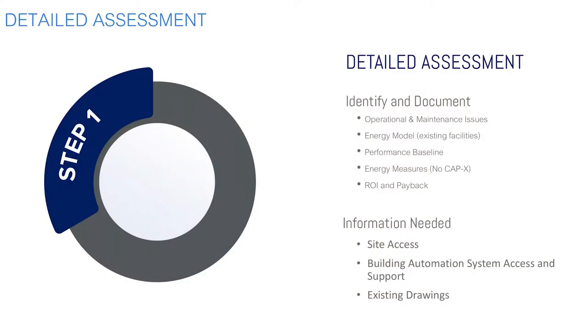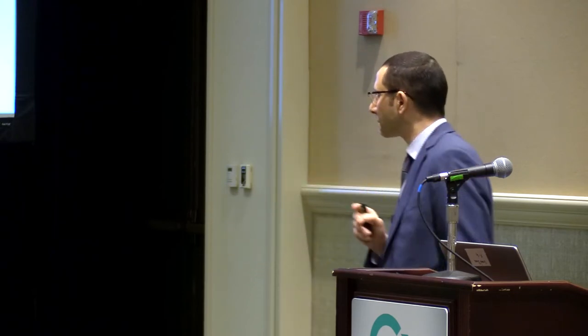How was this achieved? As Andy indicated earlier, we used the detailed assessment. We wanted to understand how the facility operates right now. Typically, I really don't care how it is designed, I care about how it is running right now, how the owner operates this building. I want to understand what are the limitations of the design, and what is the capacity of the system to do different things. Then we want to come up with new performance measures. We want to redesign the system, so to speak, but only by making the building automation system more predictable and smarter, able to change as the load changes in the building.